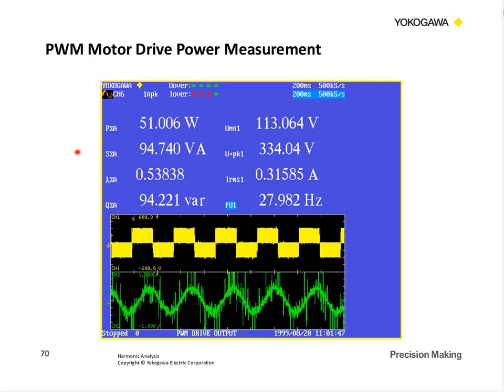Here's a little bit of information to look at on a PWM motor drive. Here's our pulse width modulated voltage, where we chop the voltage and then we vary the frequency. So it's a very distorted waveform, and we get a lot of switching noise on the current side because of the PWM on the voltage. Here we're looking at the total power, total VA, and the total power factor. We can look at the VAR, and we had the drive running kind of slow at 27, 28 hertz.